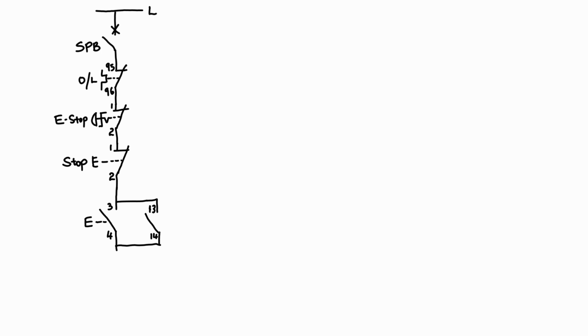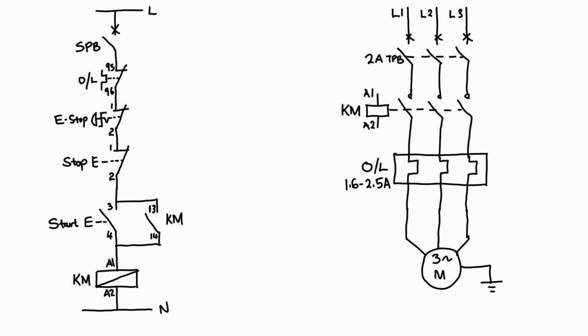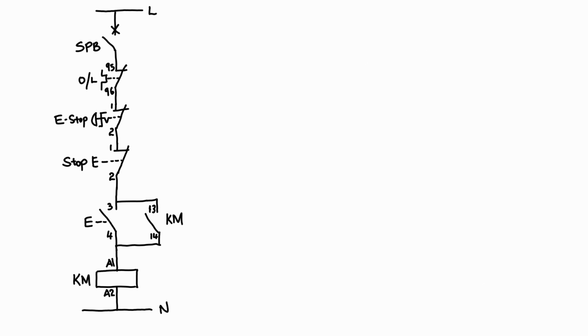And next up is the contactor coil, which is A1 and A2. Now, I know that a lot of you have got different graphic symbols that you use for the contactor block. Some put a diagonal line inside here. Whatever you do, it doesn't matter. And some do this, whatever, as long as there's some form of uniformity in the symbols that you use. But for me, I just prefer to leave it blank because it saves time, not too many lines drawn. So this is our contactor. Here I just put my line at the top, and I just labeled it live.